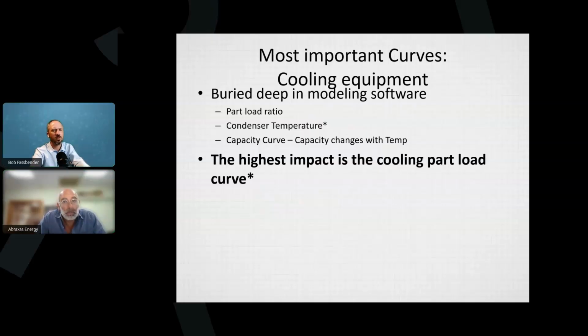That's interesting. Yeah, because the smaller the deadband, the more often the cooling or heating is going to come on, right? So if you have a deadband of 1 degree, you're going to have a lot more heating and cooling. You increase your deadband to 5 degrees, a lot less heating and cooling going on, both. Yeah. Was that in residential software? No. Okay. I was thinking the thermal mass would prevent that. But yeah, if you have it at 1 degree, that's going to cycle a lot.